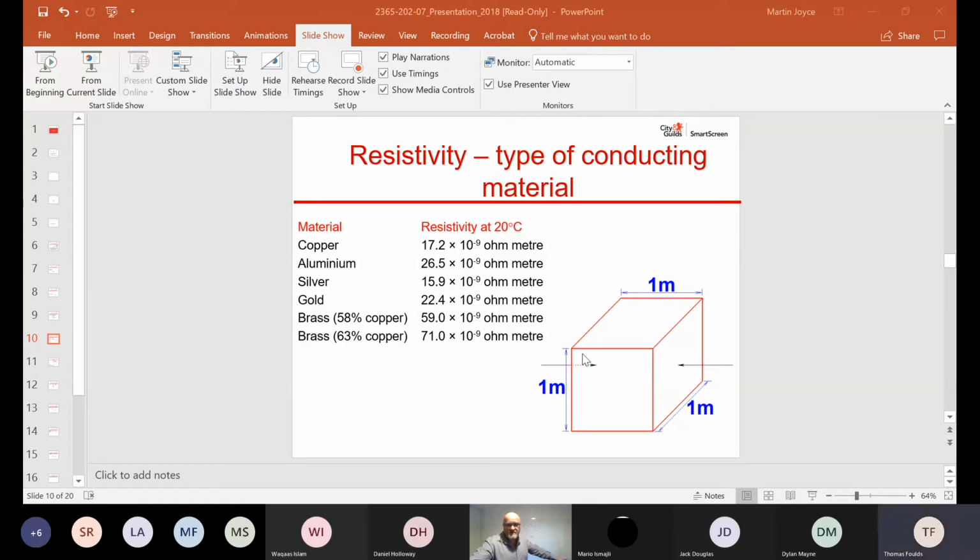I'll change that, but the point is, they've got it wrong on the PowerPoint. This is the formula we're using, and this is what they use. The rho, like a bent over P, times L, and that's always for copper, the fixed constant, 1.72 10 to the -8. If you try 9 with that one, your readings will be ridiculously too high when you do the equation. I've already been through this before. They've made a mistake on the PowerPoint, so please ignore that.